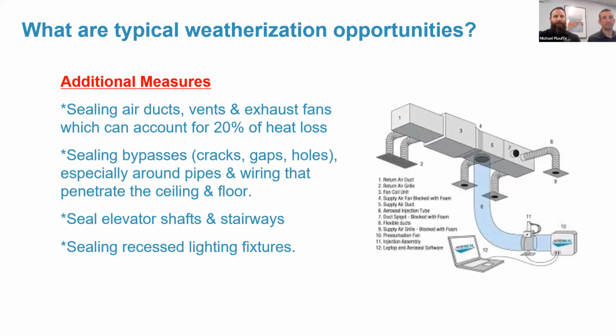In terms of the intentional forced ventilation, sealing the air vents and ducts and exhaust fans can significantly increase the efficiency of the system. I touched on this earlier, but it is very crucial to ensure that as you're paying to heat and cool this air, you're actually getting it to the intended spaces and minimizing any losses through the system.